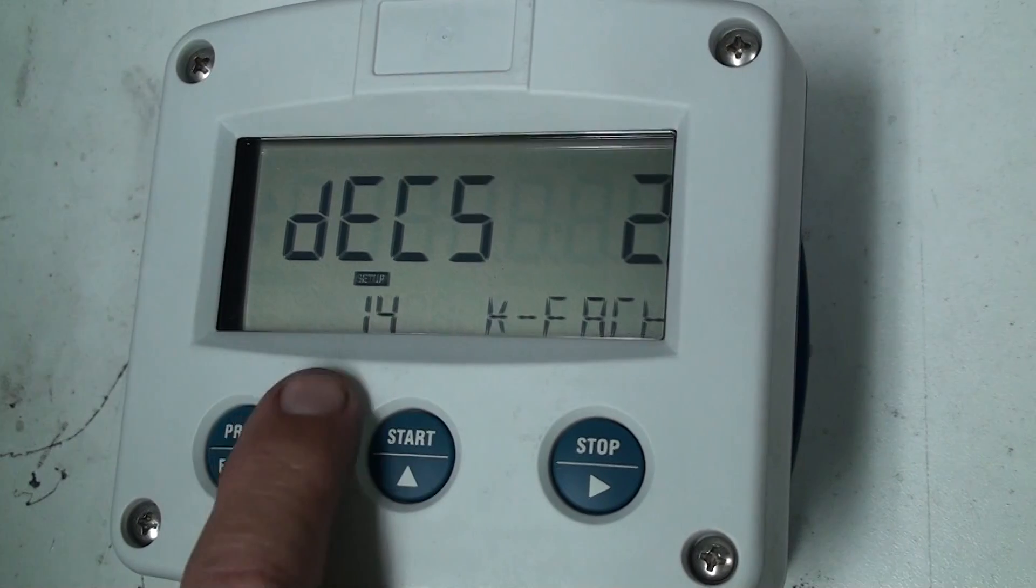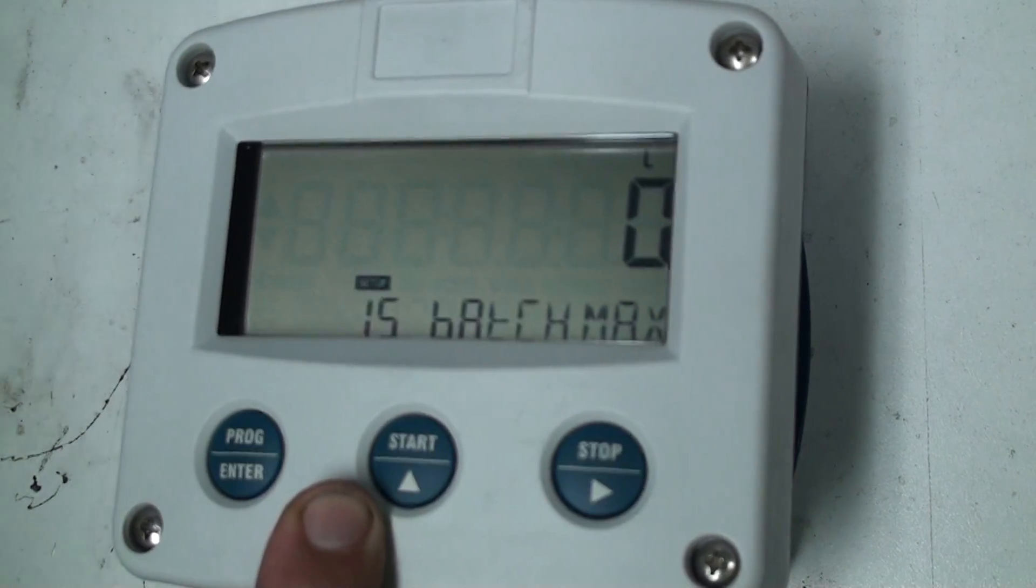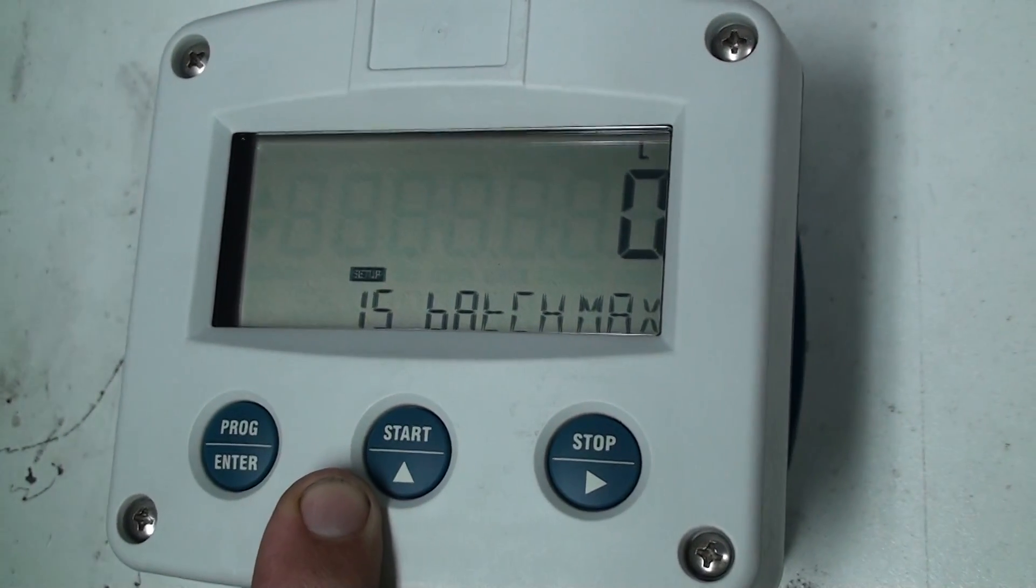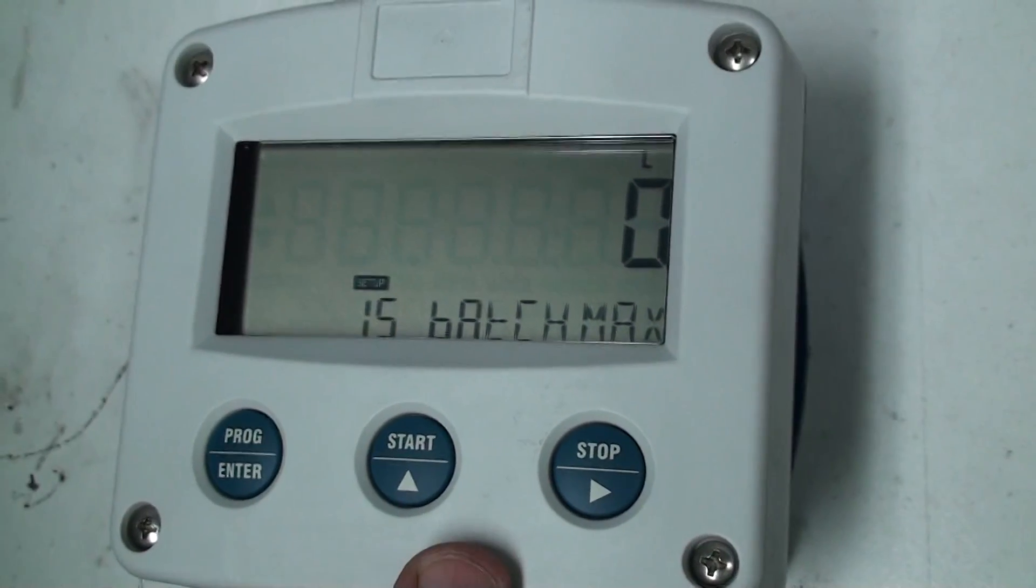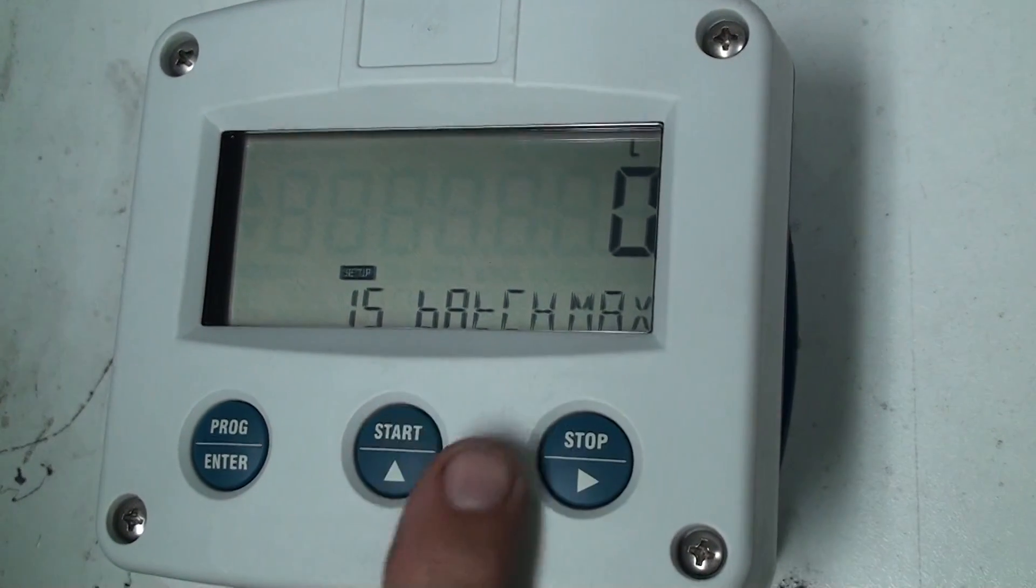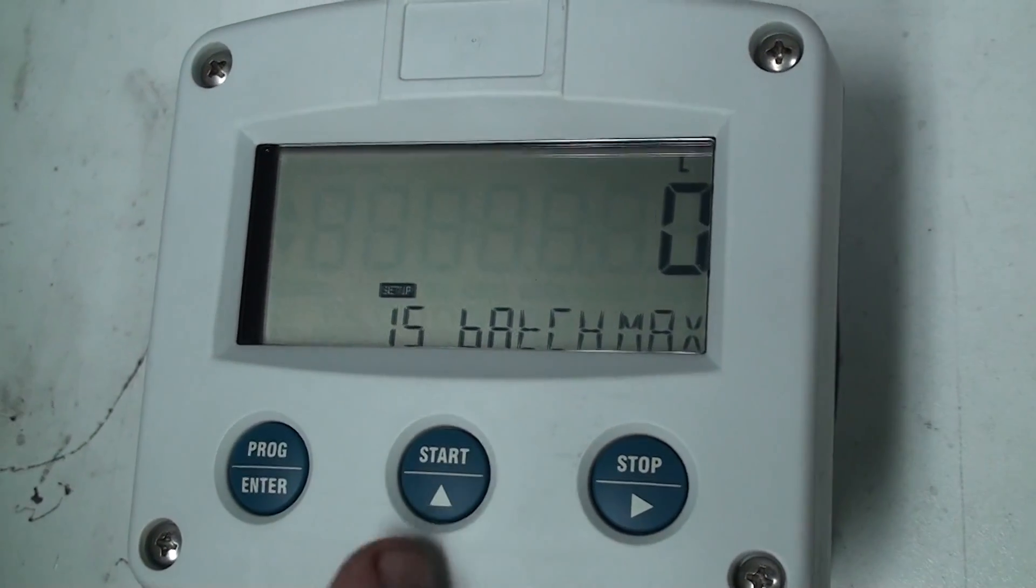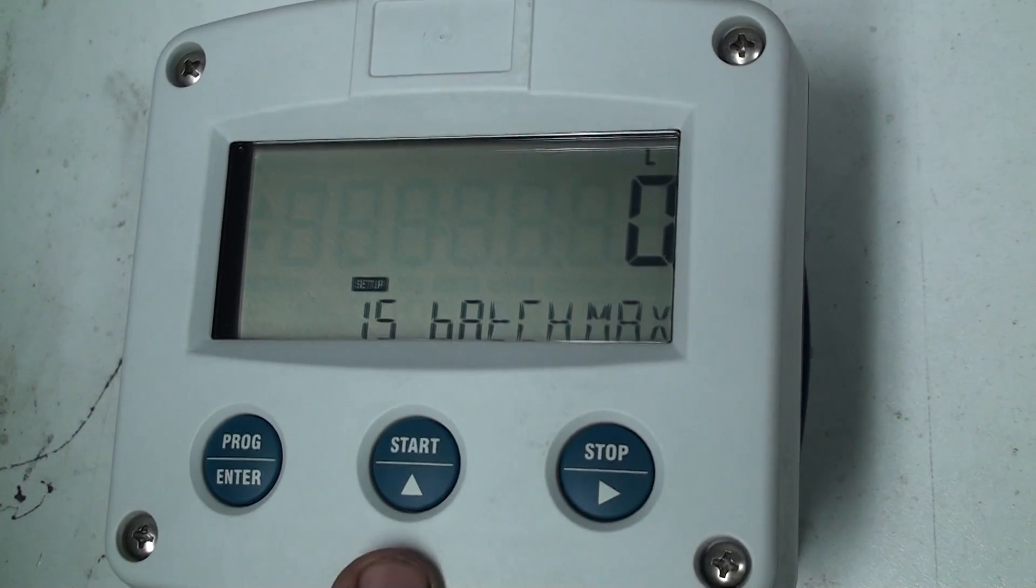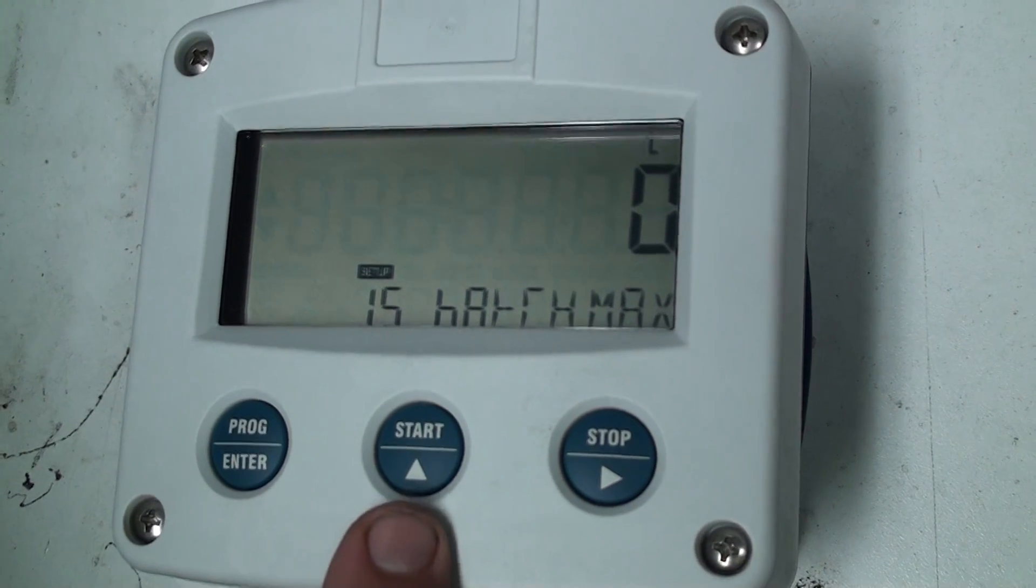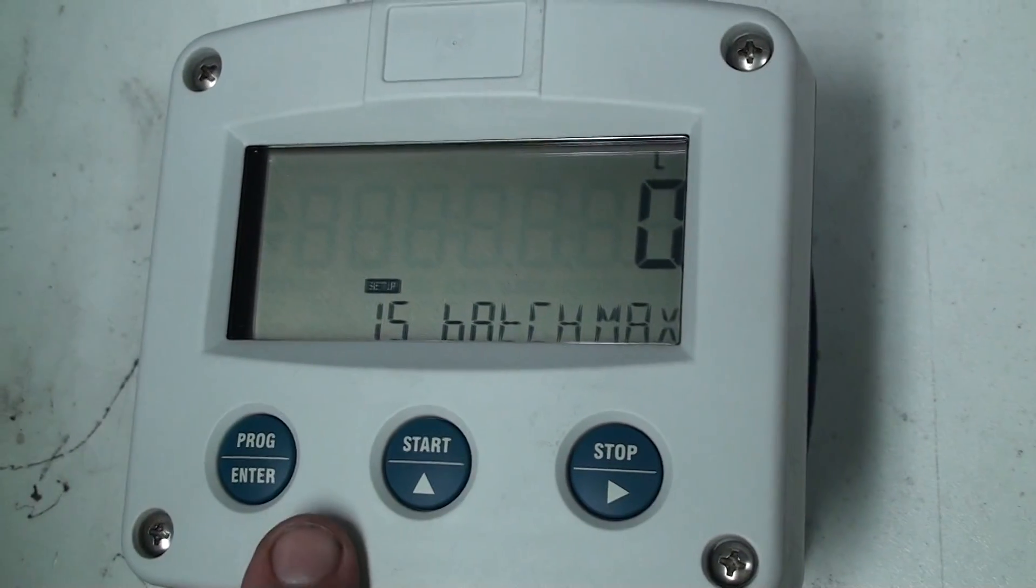I need to go to 15 and that's the batch max. What that is you can set a maximum if you're batching 500 liters into drums or a container and you don't want to go any more than 700 liters or 600 liters you can enter the maximum quantity that you want. Our 2 inch flow meter will do up to 500 liters per minute and it basically goes on the volume that you need to flow into your tank or container. If your container is going to be say 1000 liters you could set this to be 1000 liters.